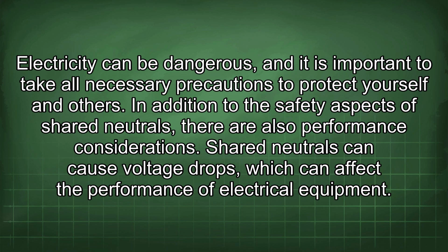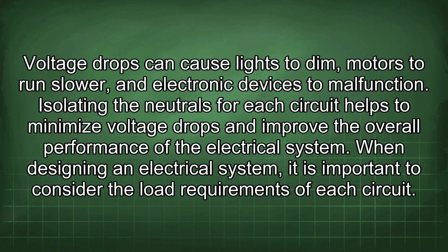In addition to the safety aspects of shared neutrals, there are also performance considerations. Shared neutrals can cause voltage drops, which can affect the performance of electrical equipment. Voltage drops can cause lights to dim, motors to run slower, and electronic devices to malfunction. Isolating the neutrals for each circuit helps to minimize voltage drops and improve the overall performance of the electrical system.